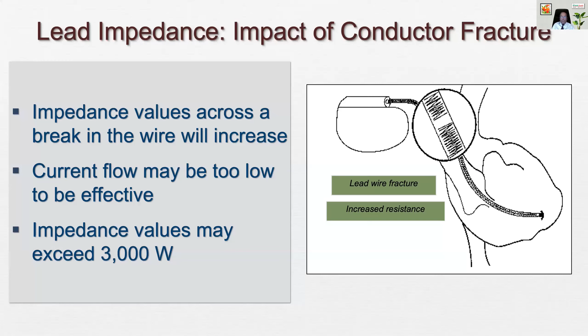A fall in impedance is less dangerous because that leads only to wastage of current flow. Often we do not do anything because at the most it will lead to some shortening of the longevity of the pacemaker, and we can change the pacemaker at that point. So why increase the number of procedures? But if the impedance is high, then the patient may be unsafe because the pacing may stop suddenly, and then there is a reason for immediate intervention in the form of replacement of the lead.